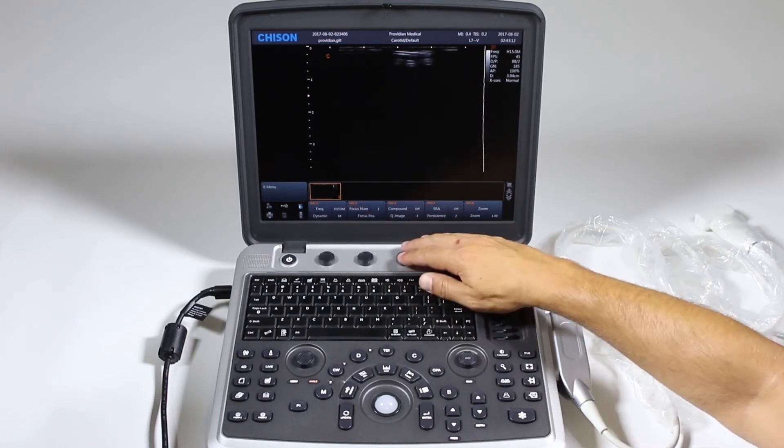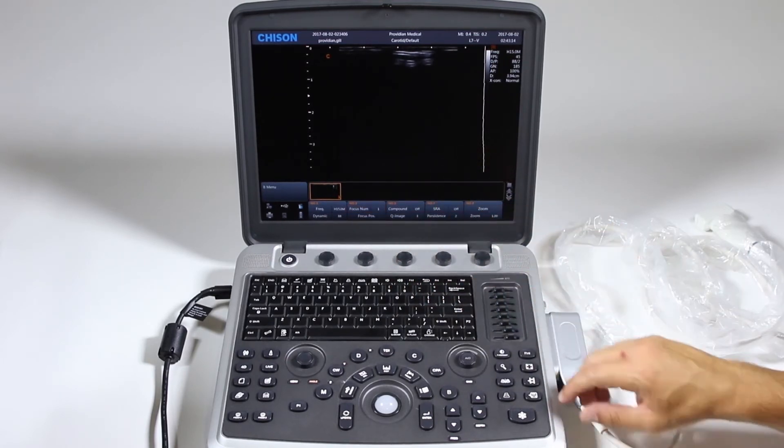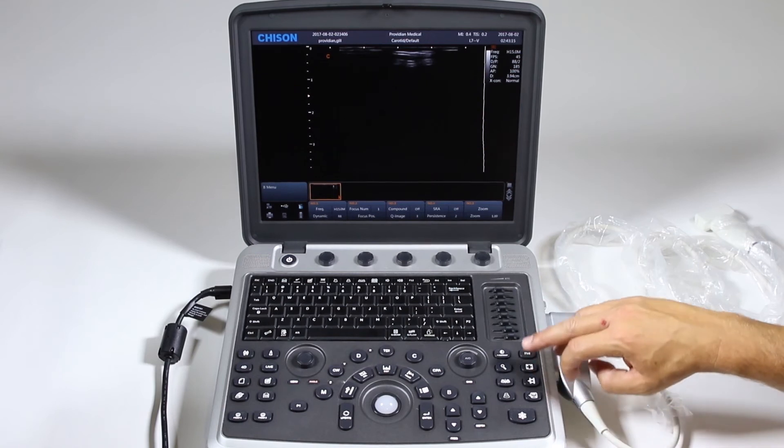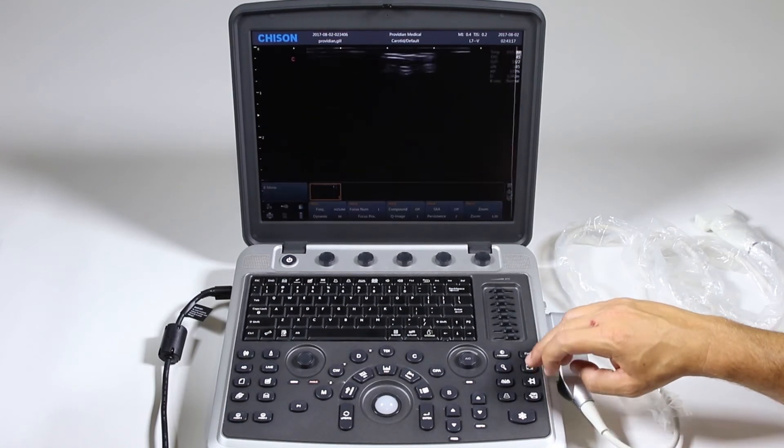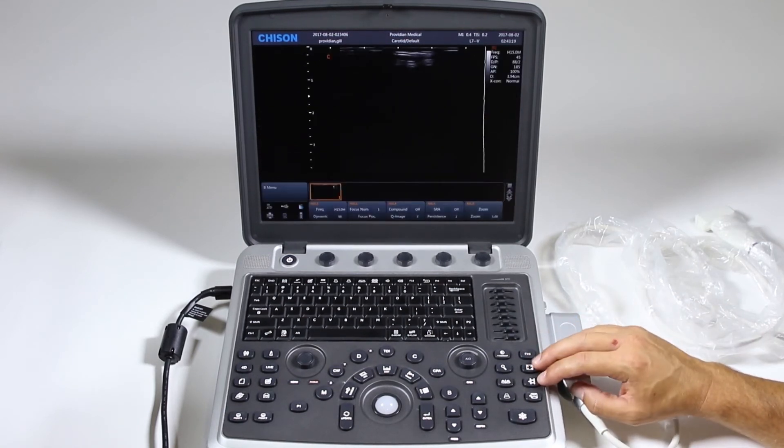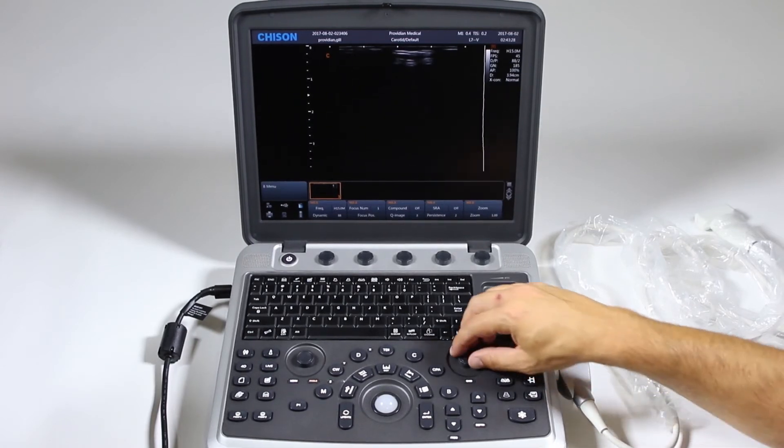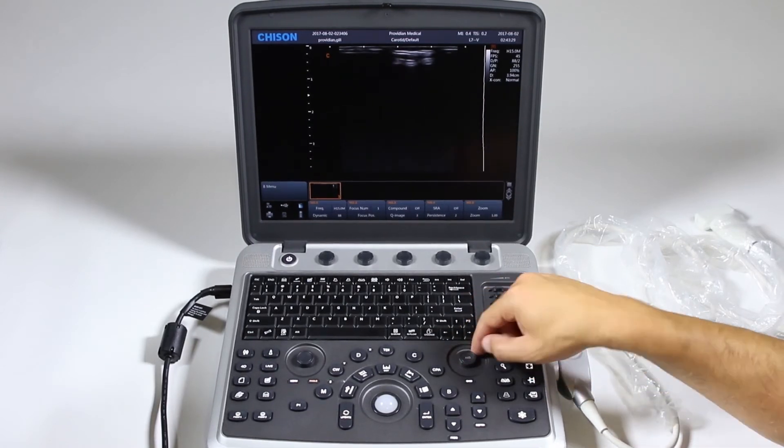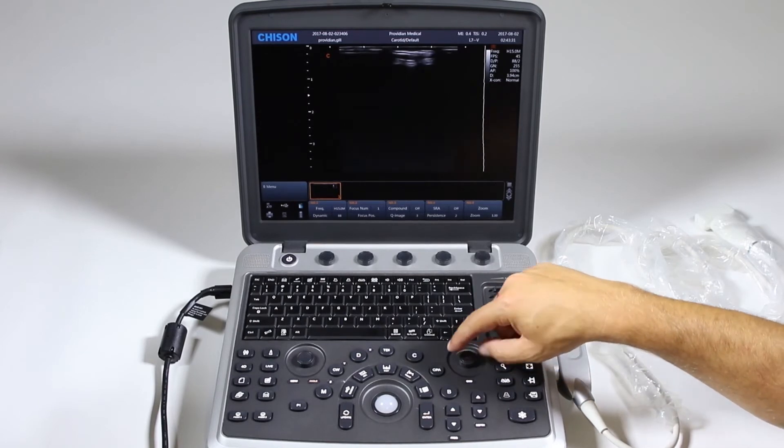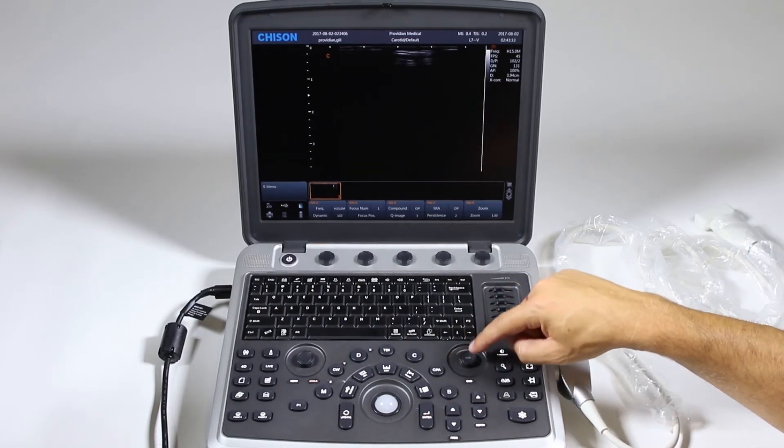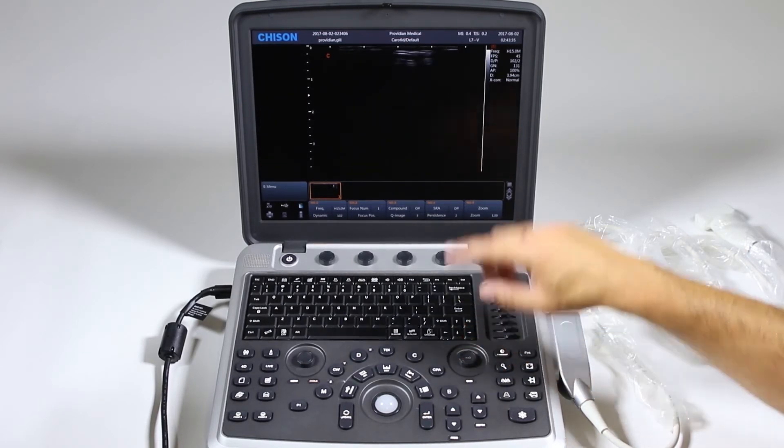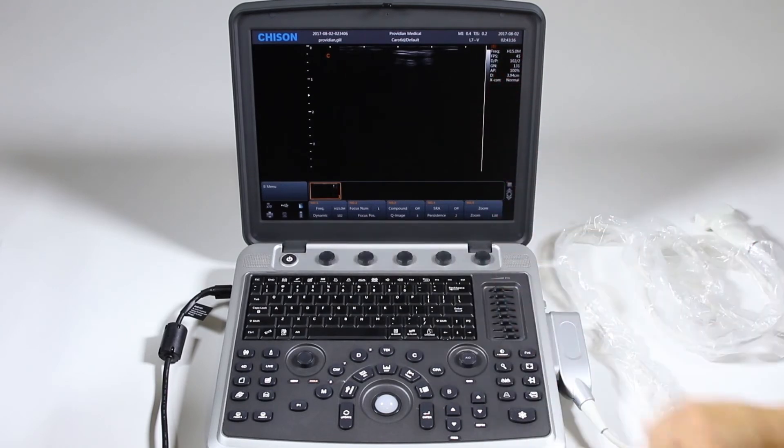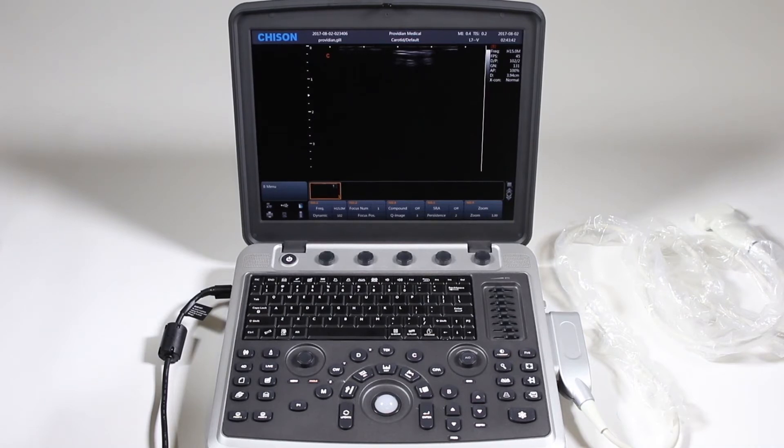Compound imaging also. Again, try all these different ways. If you want to see a larger screen, you can click this to go to full screen view. Click it again to go back to the regular screen view. Your gain control is here. Just twist it to change the gain. If you want to try its automatic image optimization, it's actually pretty good on this machine. It will try and look at your image and give you the best image possible as far as the gain is concerned.